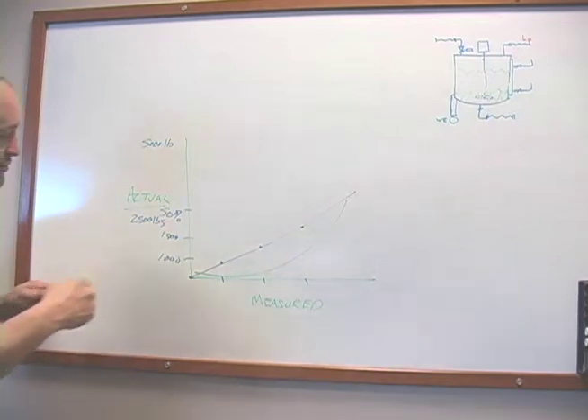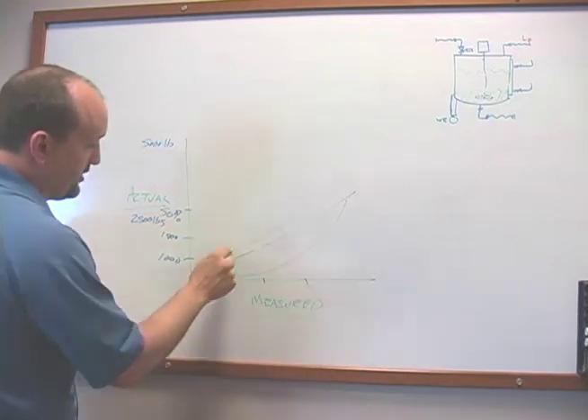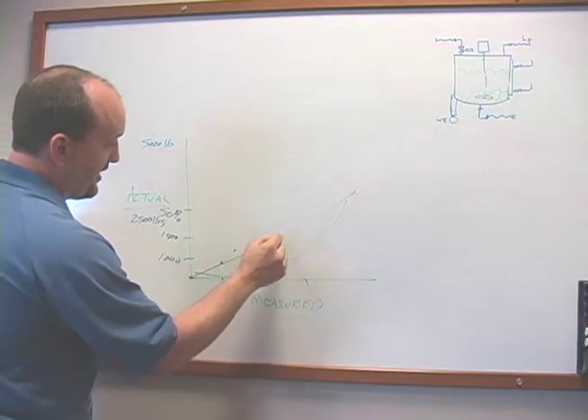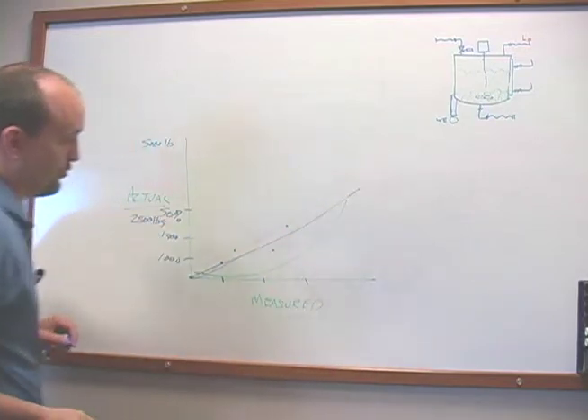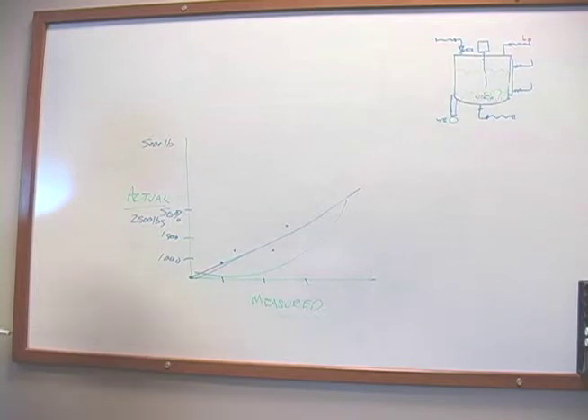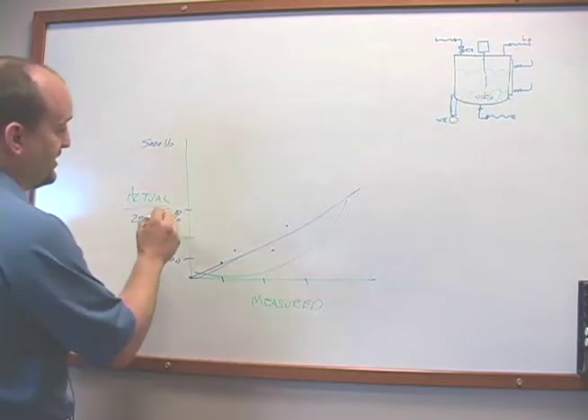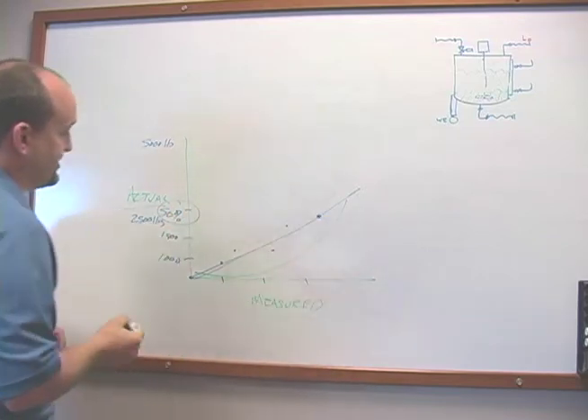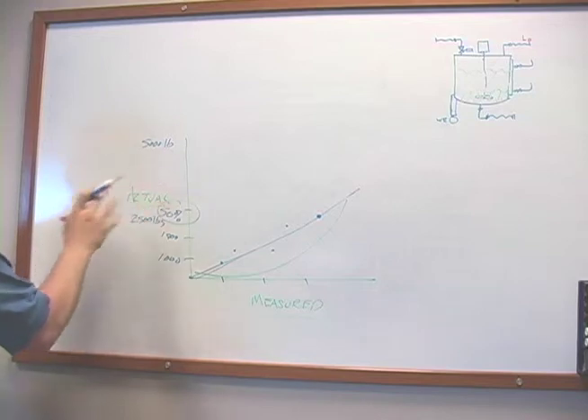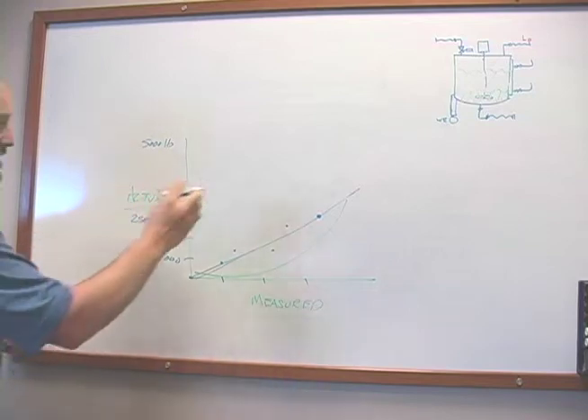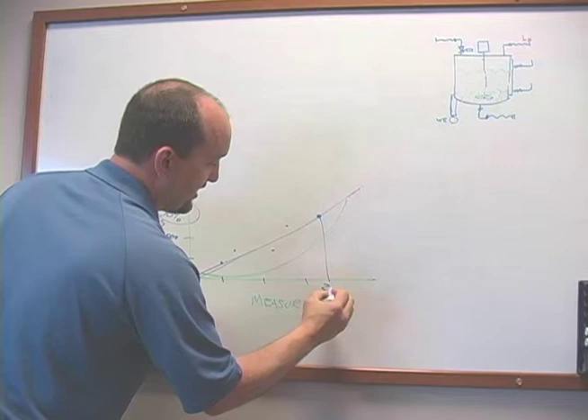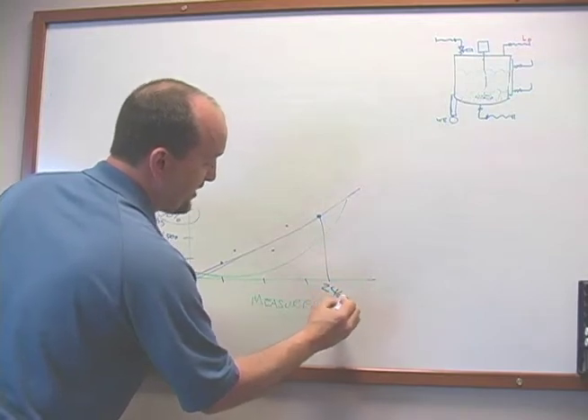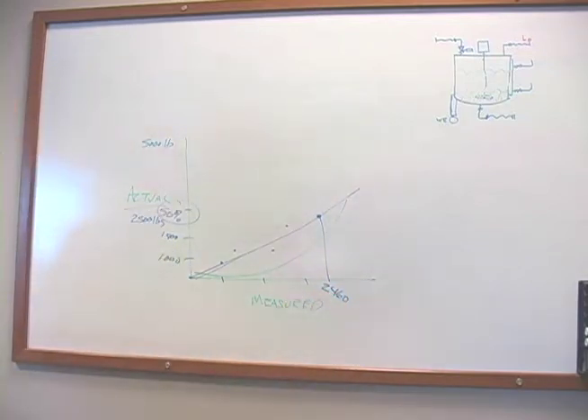At some point, you'll find through these dots, you'll find that you have a line that runs basically through the center of those. What I advise is if it's fairly close, you pick your 50% weight. So let's say at 50% or 2,500 pounds, we know we have 2,500 pounds in the tank. And our load cell says, well, you only have 2,460 pounds in the tank. Somewhere there's a line lifting up on the thing worth 40 pounds. That's what we're trying to calibrate out. It's that simple.